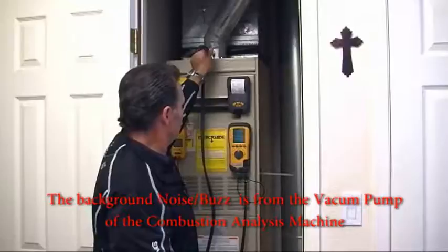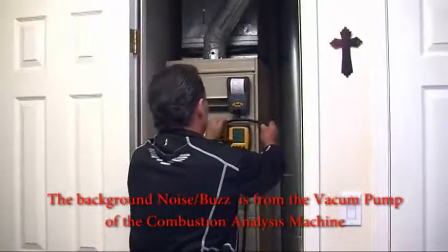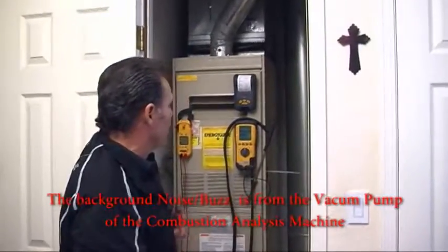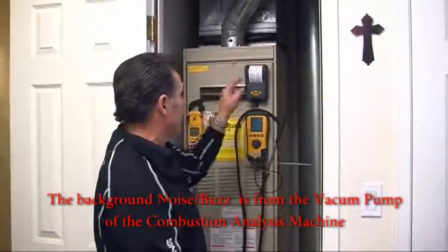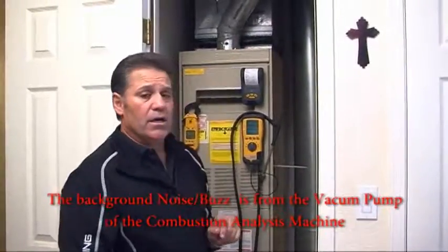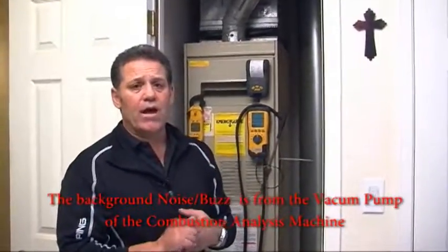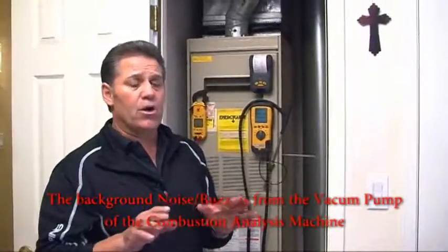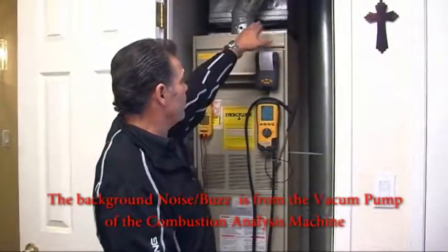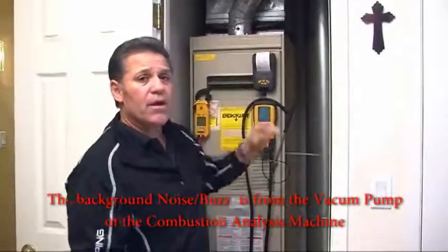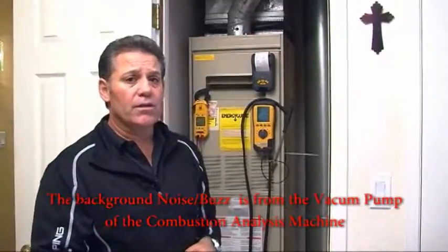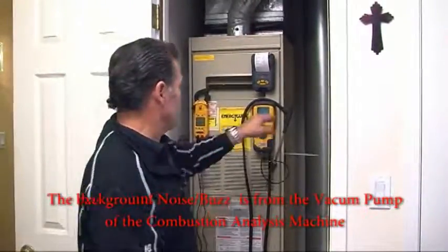Results are finishing at this point. Now, one of the things I like to do while I do a combustion analysis is test the supply going into the house, because I want to make sure that I don't have any carbon monoxide at all. If we have carbon monoxide in the supply plenum, then we have a cracked heat exchanger. It's one way to be sure that you don't have a cracked heat exchanger.